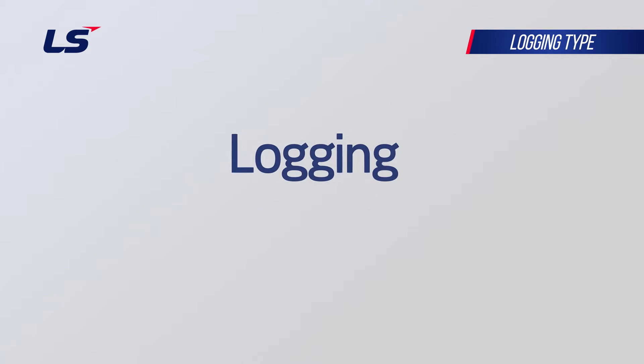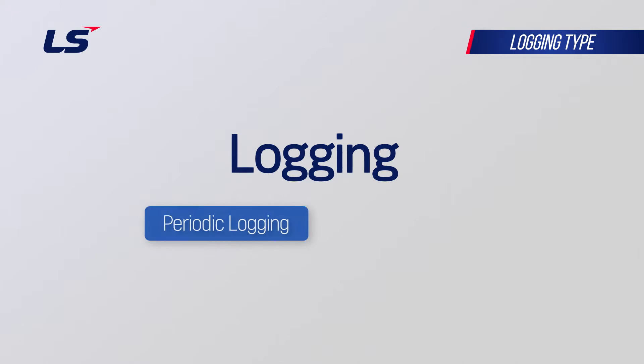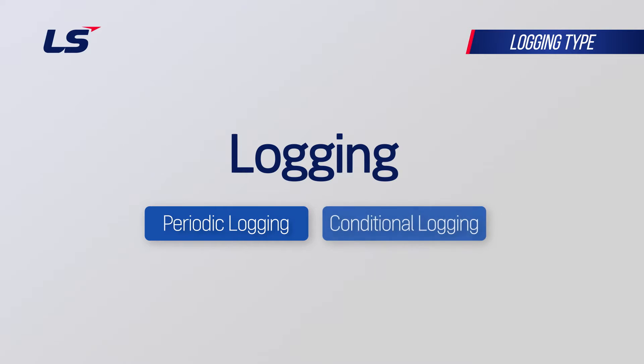If you decide which device to log, you must set the execution condition for when logging will run. There are two logging conditions: periodic logging, which requires number of repetitions and repeat period, and conditional logging, which enables logging based on the status of a bit device.